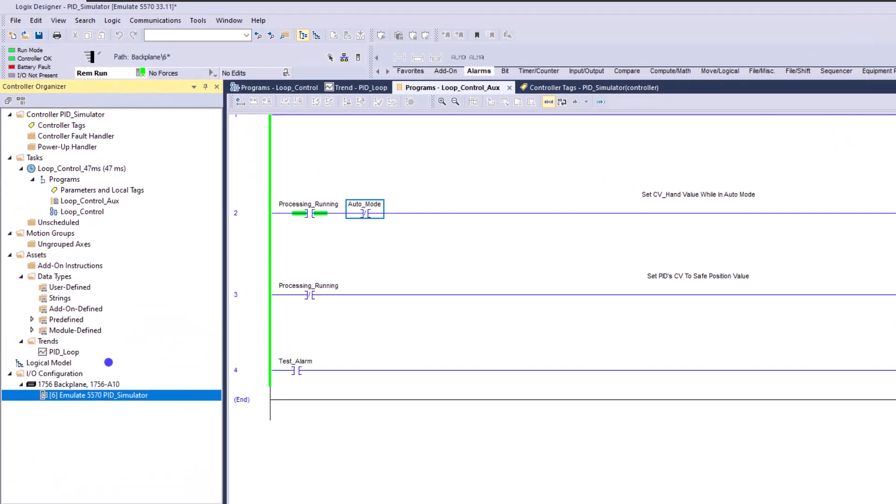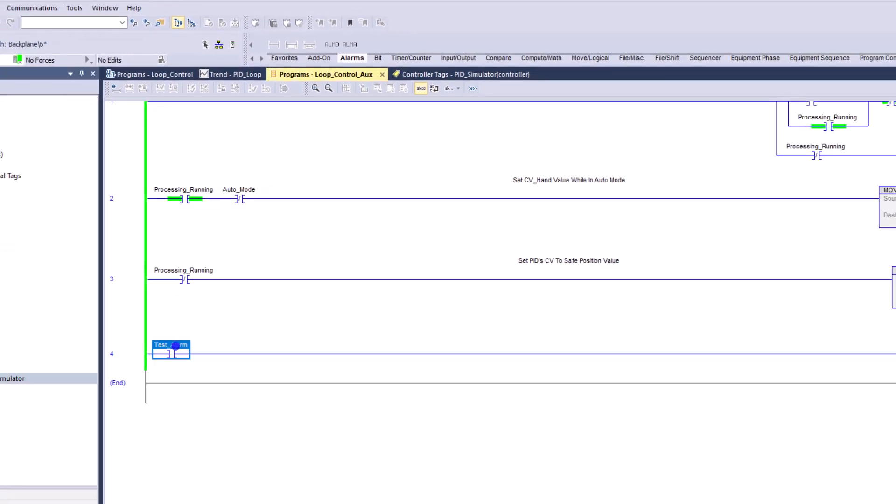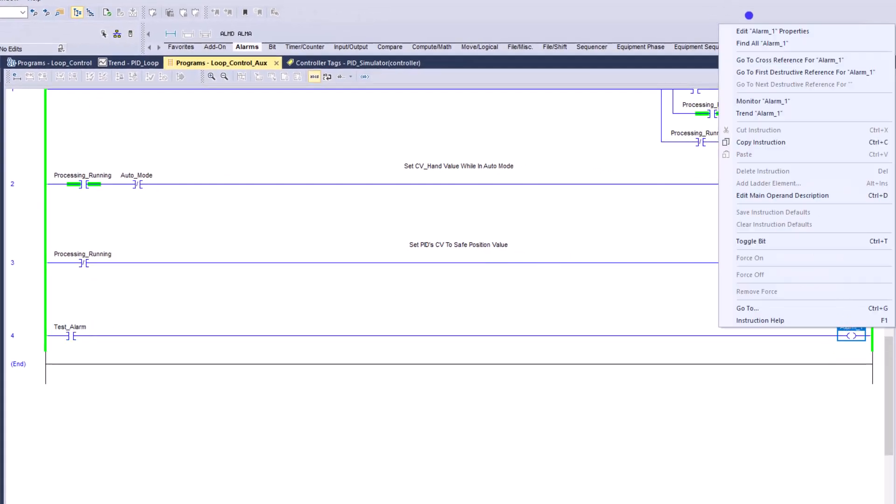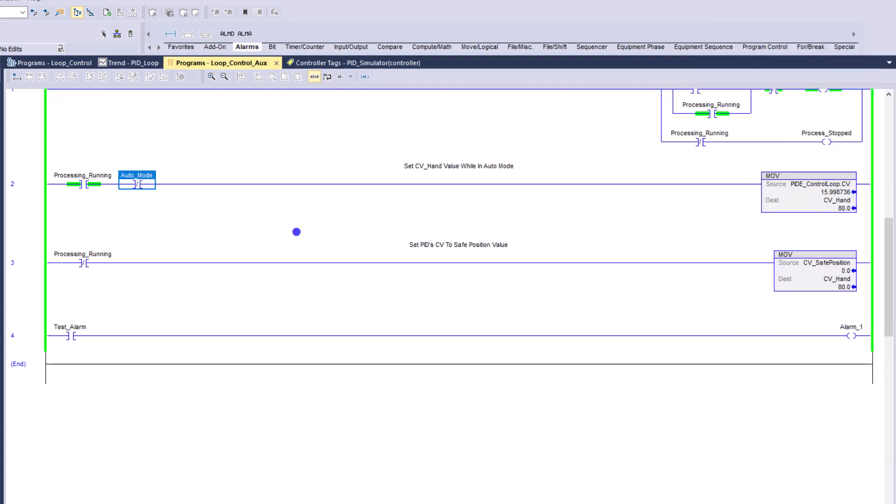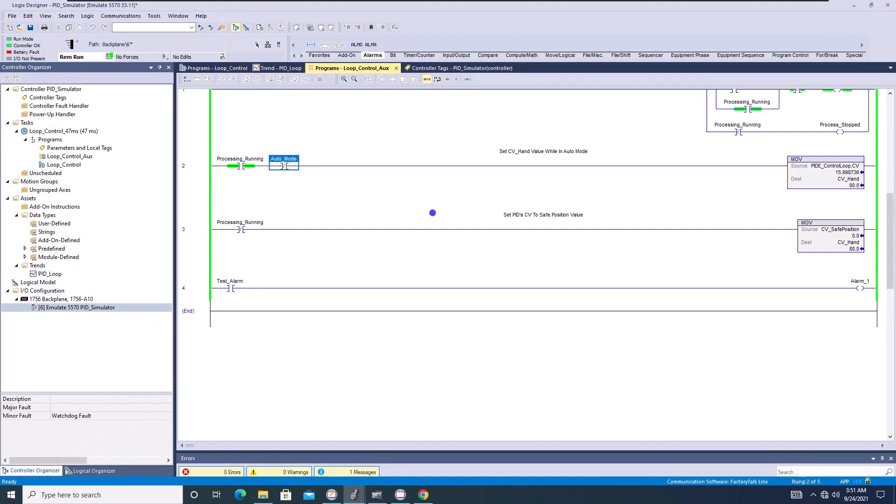This is an emulated 5570 processor that I currently have running. You are not allowed to use the alarm manager. I can come over here and actually do the same exact thing, test this, and I do not have the ability to add it to an alarm because it doesn't have that functionality. Now when they do escalate the emulated processor or the emulated version to a 5580 processor, then yes, the possibility would probably be there.